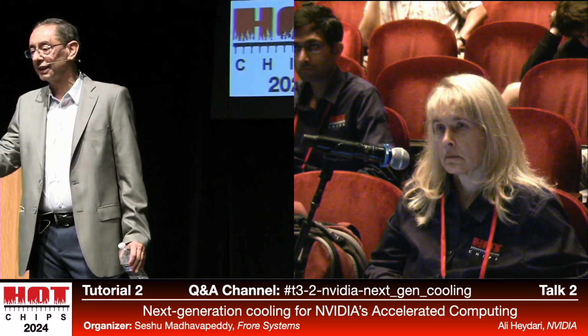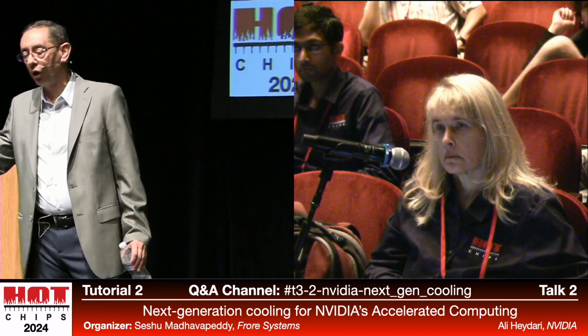Now, that's not a suggestion that we're going to have that level of chip density. But talking about physics, that's where I think the physics is going to bend, where we don't have enough liquid going through anything like a best-in-class cold plate, that's probably at 0.015 degrees C per watt, the typical best cold plate, that can maintain the case temperature on that GPU to that desired level.